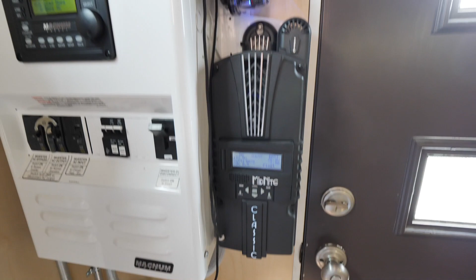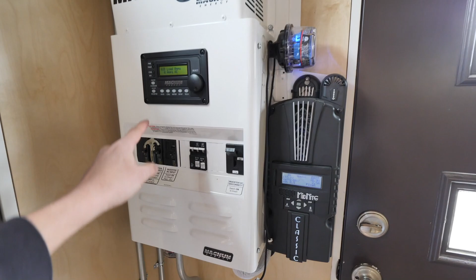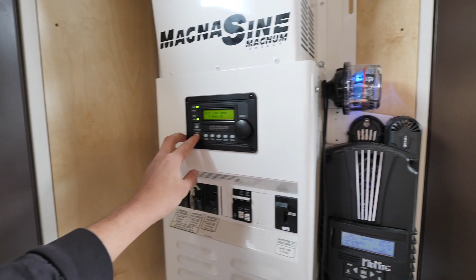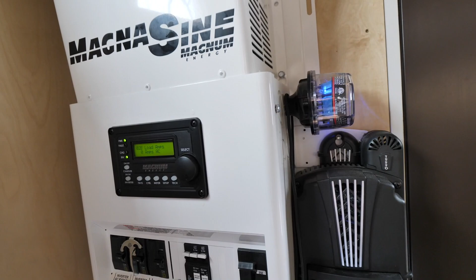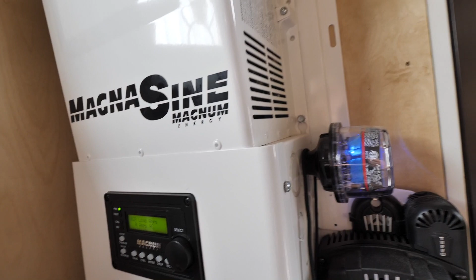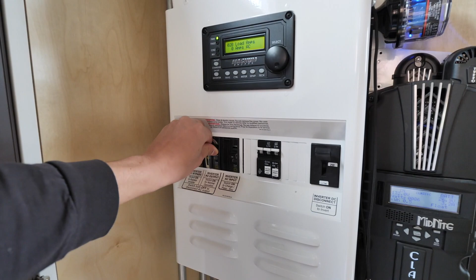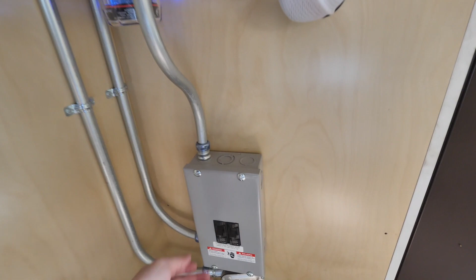But in order to show that, I have to put a load on the system. Let me go ahead and turn on the inverter. Right now it's trying to detect a load, and there's a little pulsing sound during this process. When I turn on the circuit breaker at the main panel, and then down here at my sub panel, you can hear the inverter is actually on. I believe if it detects 5 watts of draw, the inverter turns on.